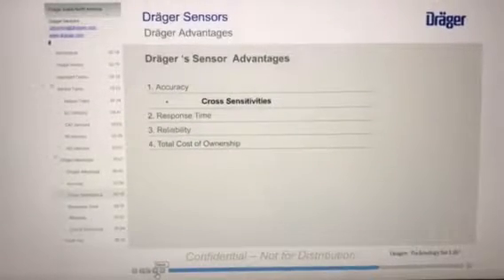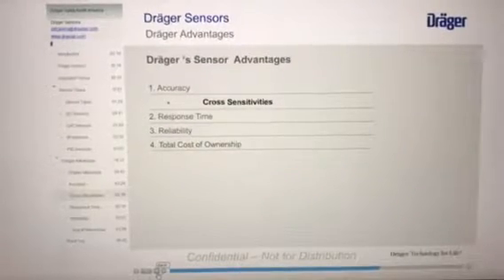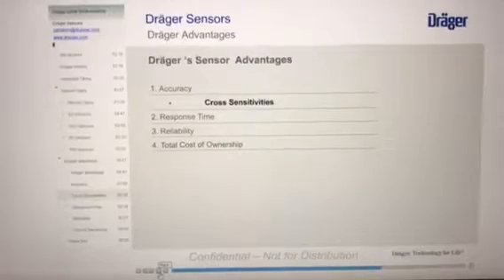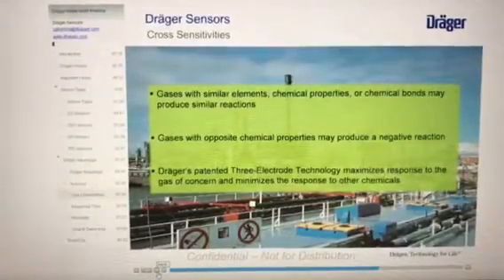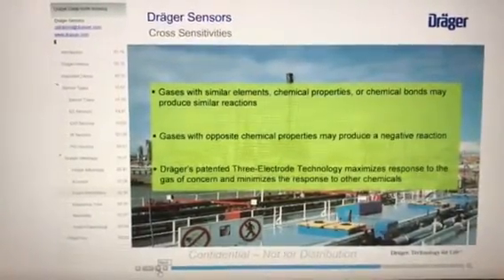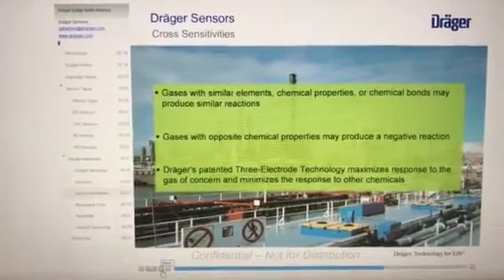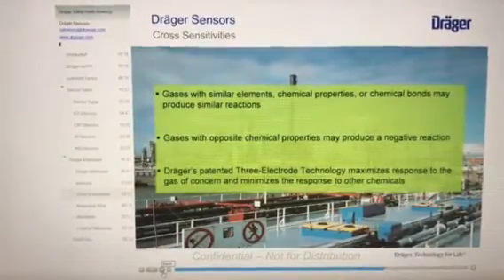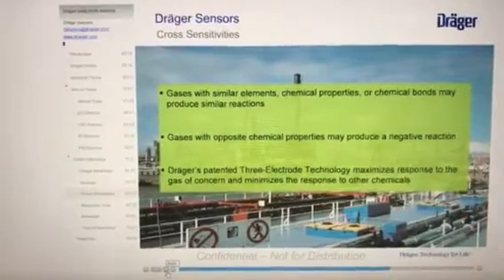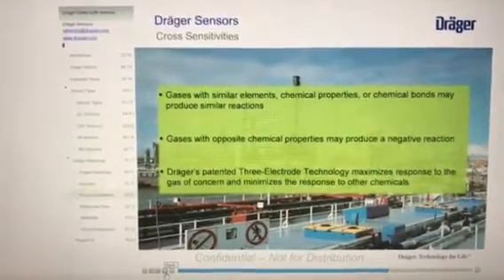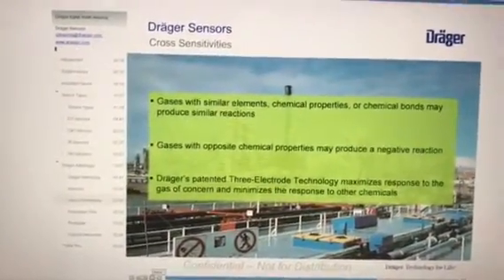Now we will discuss another aspect of sensor accuracy by looking into sensor cross-sensitivities. All sensors have cross-sensitivities, which means that the sensor reacts to another gas that is not the target gas of the sensor. Gases with similar elements, chemical properties, or chemical bonds may produce similar readings by the sensor even if the target gas is not present.